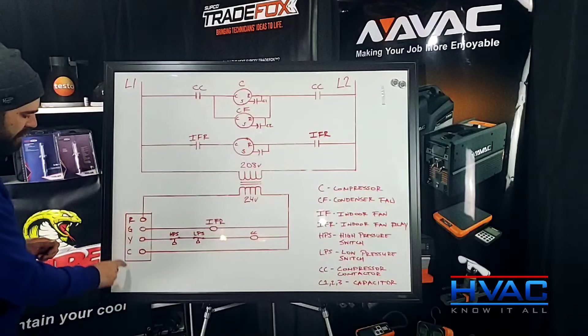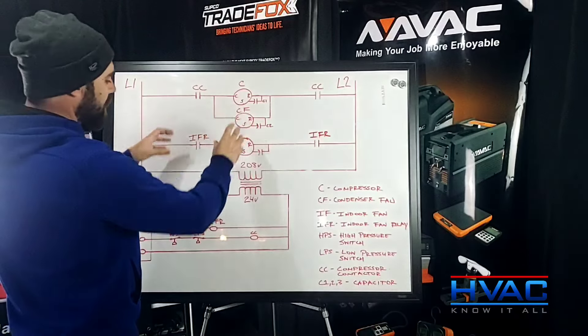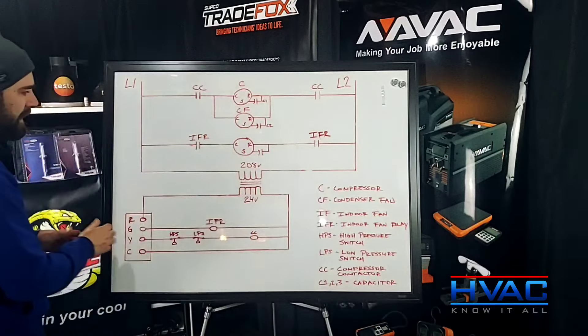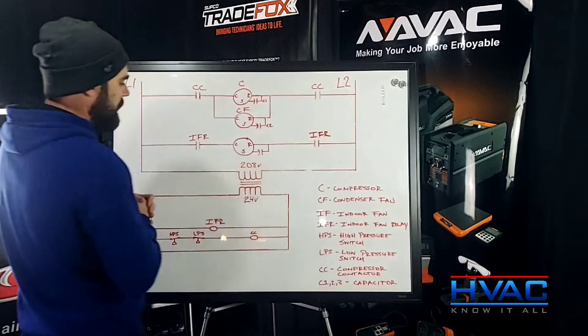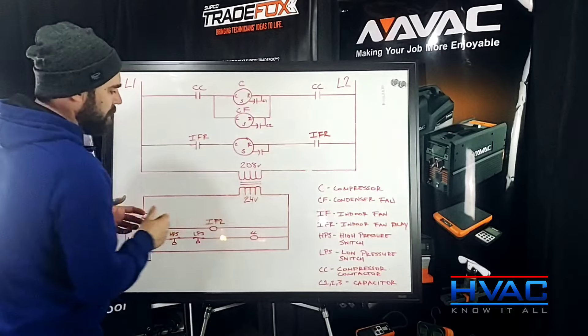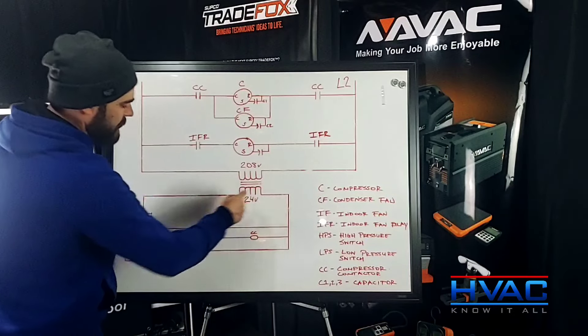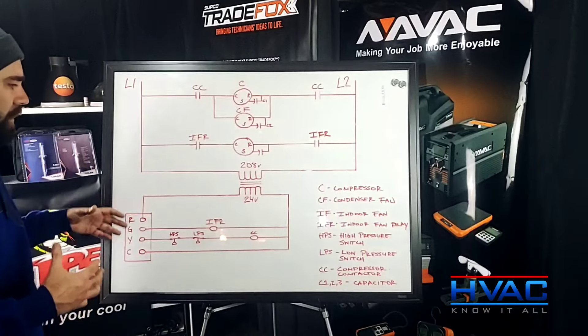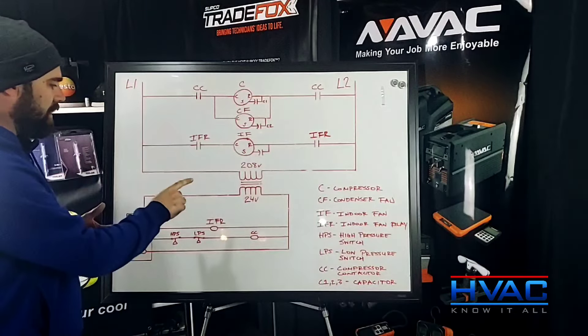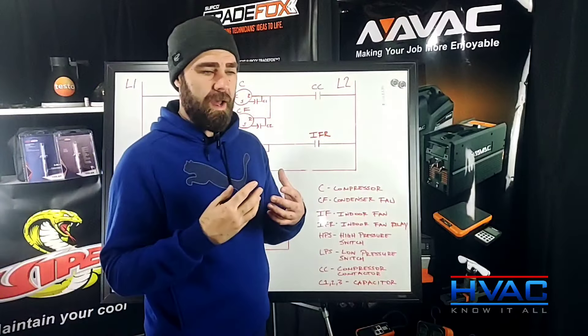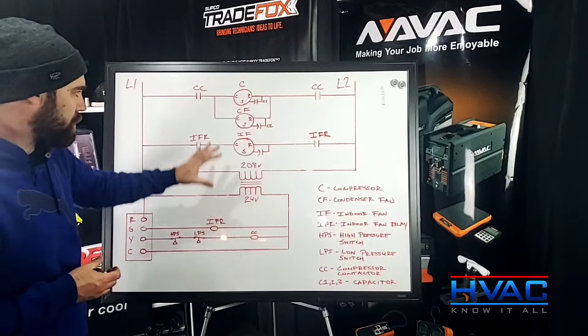And this here is your thermostat. I didn't label it because it would be too small to read in the video. So we have the high side, the low side, our transformer, our thermostat, and our legend. Just keep in mind that we have line one and line two — it's not line one and common. On this lower side of the system, 24 volts, we do have a common here. So we're going to leave 24 volts out of here and on this side we are going to have a common. Now let's get into this a little bit further and I'll show you how I learned to read diagrams — using this finger right here. The way I learned is I'd start with my finger and put it on the place that was the beginning of what I wanted to find out. You always want to start on the low voltage side because all of this here controls what's happening on the high side.